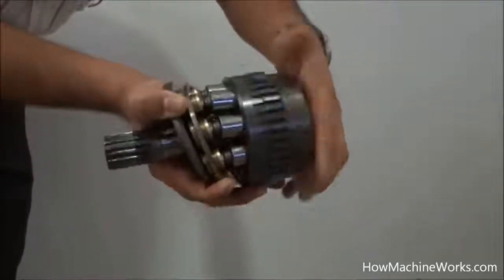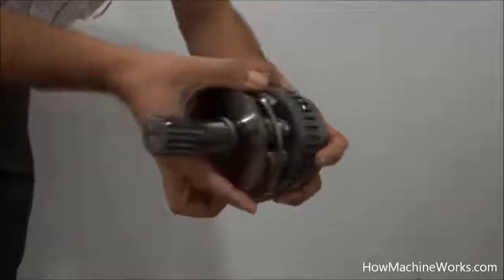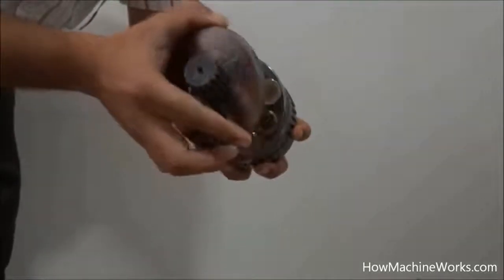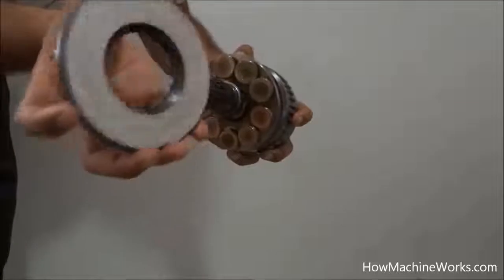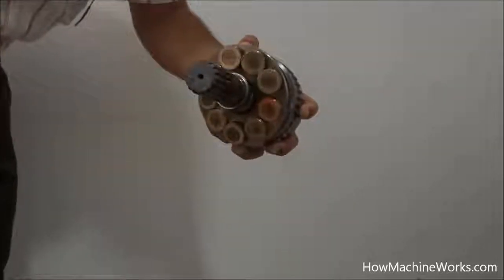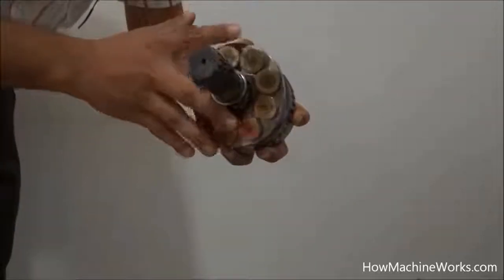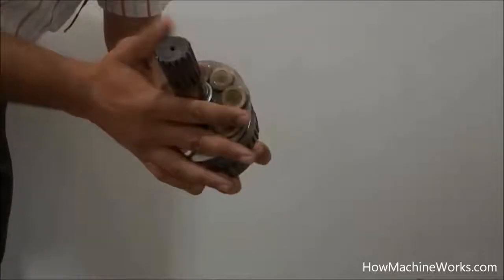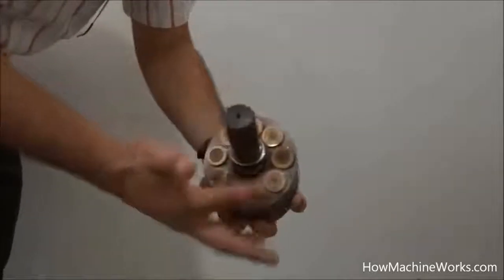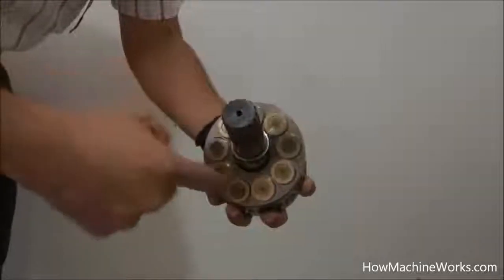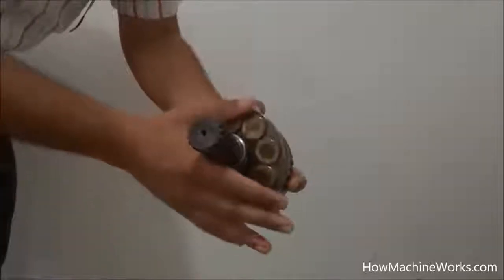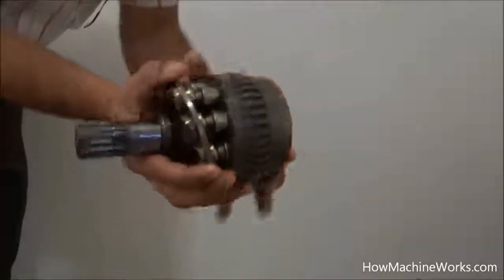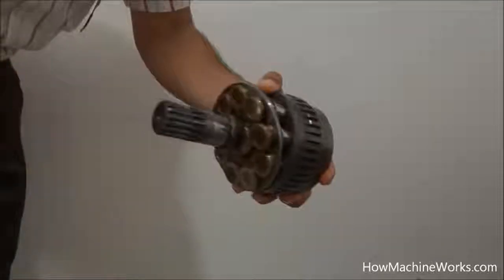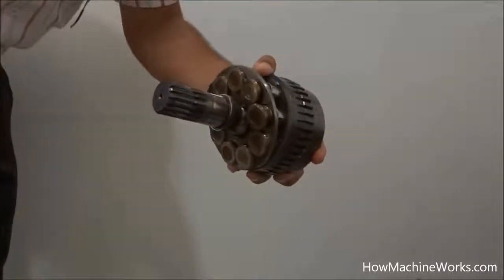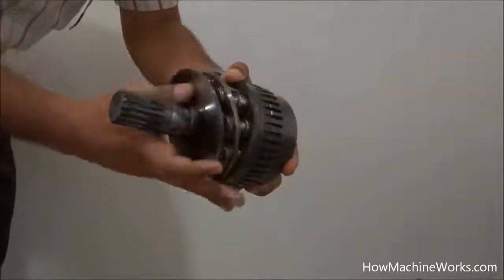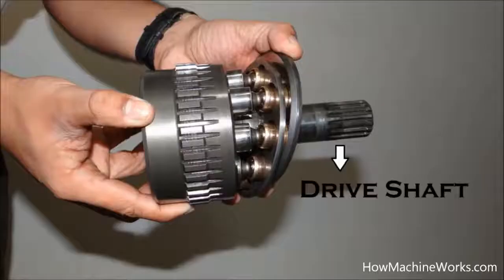So when the swash plate is vertical, there is no flow, and as the swash plate angle changes, the flow varies depending upon the angle of the swash plate, and the swash plate angle is controlled by a valve according to the load and the requirement. So that's the rear side of the piston which is sliding over the swash plate over there. Okay, now let's have a closer look and identify each component.